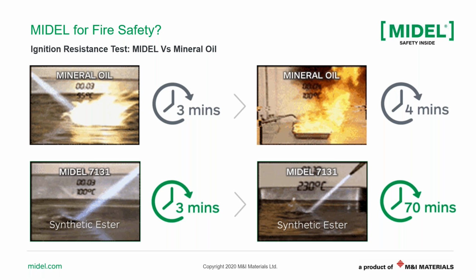Now, for mineral oil, if you look at the top left picture, after 3 minutes, the bulk liquid temperature reached 95 degrees, and then you started having localized ignition, a small flame. Further 1 minute more, the entire pan catches fire, as you can see in the top right picture. And this is burning fiercely with heavy smoke. Now, the bottom ones are for equivalent scenario with MIDEL 7131 synthetic ester. The same amount after 3 minutes, we expose the surface of the liquid to the oxyacetylene torch.